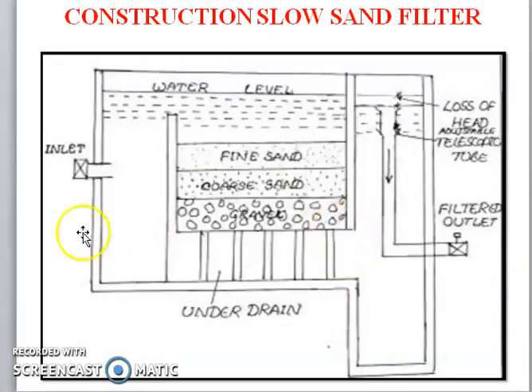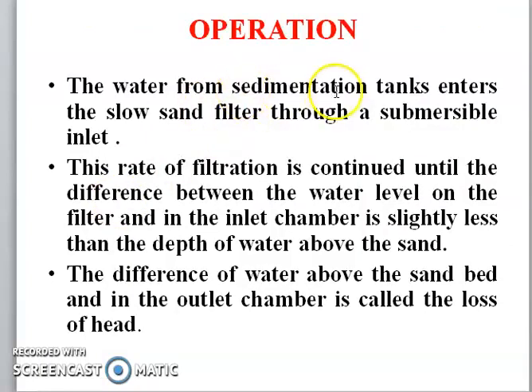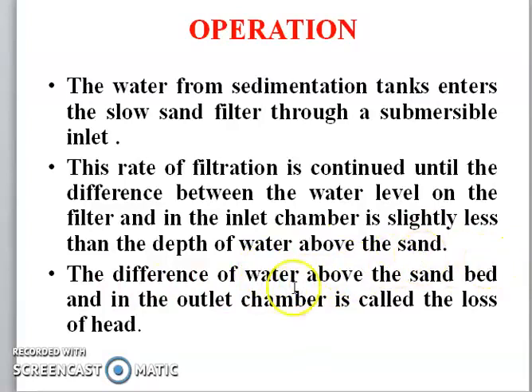This is the slow sand filter. It has an inlet, filter sand, fine aggregate, coarse aggregate — water passes through the aggregate layers and is filtered. This is the outlet. In operation, water from the sedimentation tank enters the slow sand filter through a submerged inlet. The rate of filtration continues until the difference between the water level on the filter and inlet chamber is slightly less than the depth of water above the sand. The difference between the water level above the sand bed and the outlet chamber is called loss of head.